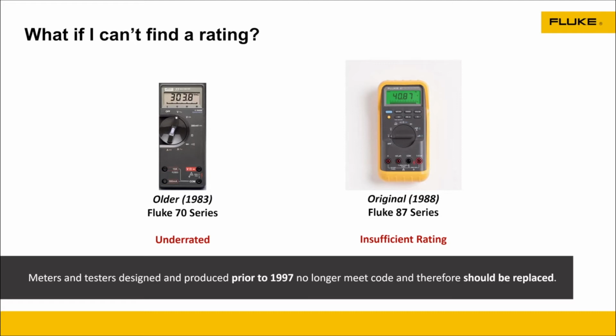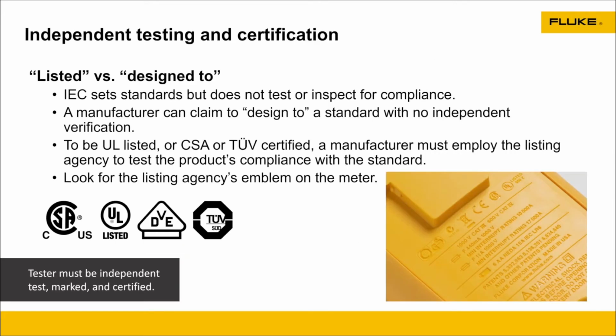With that being said, I hear this a lot at trade shows. Somebody comes by the booth and says, "Hey man, I love your meter. I'm actually using the meter my father gave me." Or I've even heard, "I'm using the meter my grandfather gave me. It's a Fluke and it's still going strong." But I have to have this type of conversation with them: the safety ratings of that meter have changed, and it doesn't qualify for some of the voltage levels it was used at. So just know what the rating of your meter is. That's really the key conversation, because again, it's all about safety.